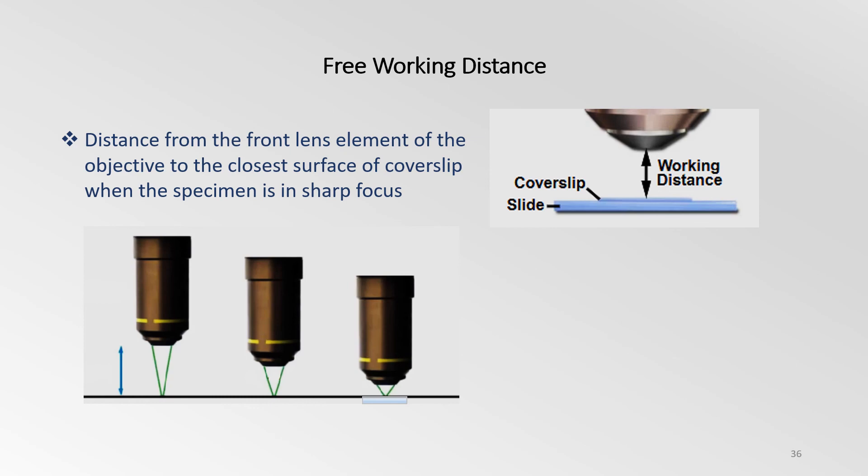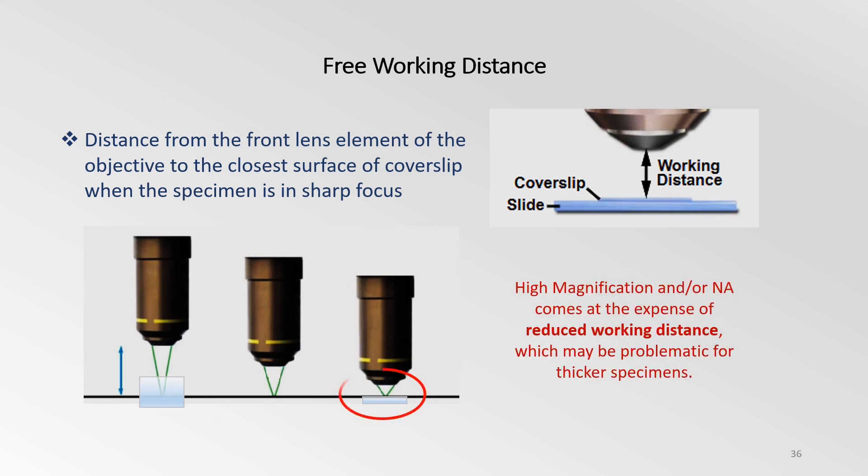But when you are imaging samples that are in thicker vessels, such as plastic well plates, you will probably need an objective that has a longer working distance. High NA objectives usually have very short working distances. So if you have a thick sample, you might have to consider instead a lower NA objective with longer working distance.